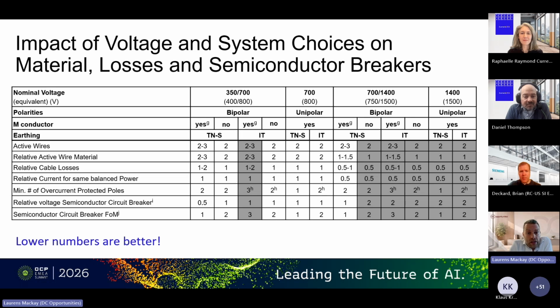In the next row, we look at the relative active wire material, and there obviously also the more wires we have, the more wire material we use, depending on the thickness that can vary. But then also as we go up in the voltage, you see on the right half of the table, we get a factor of 2 lower current, basically, because our effective voltage in our power system is higher. So we need to distribute less current, and in order to carry that with only half the current, we in principle only need half the copper for that. So that makes a big difference there.